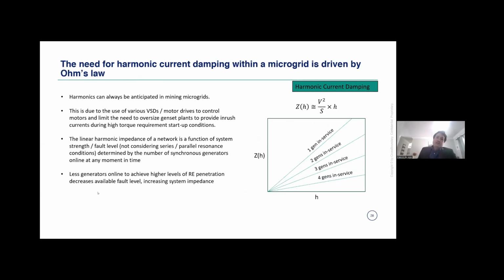And then finally, the last application we applied was harmonic current damping. And why is this important in microgrids? I think it's important to understand that, first of all, microgrids will have various sources of harmonics, whether it be VSDs or motor drives, etc., because we always need to manage the amount of startup current or inrush current within these systems, because we don't have the advantage of utility that can just quickly inject high levels of power to start up a large mill or motor. So having these VSDs on the system would always cause a harmonic current to be on the system.